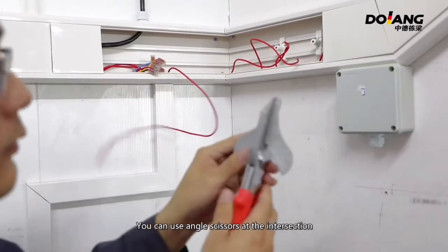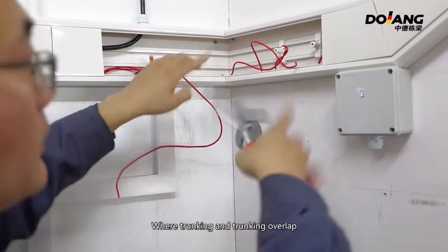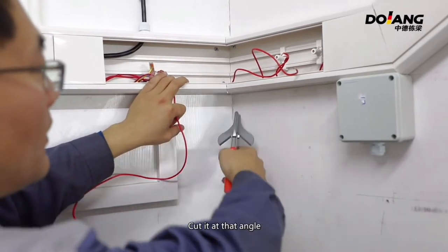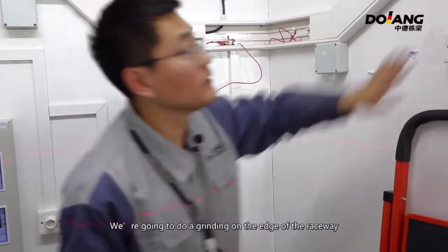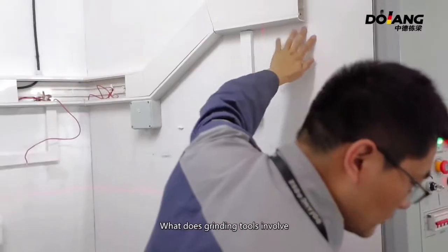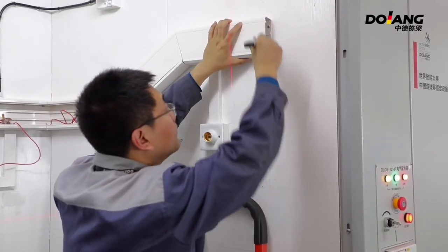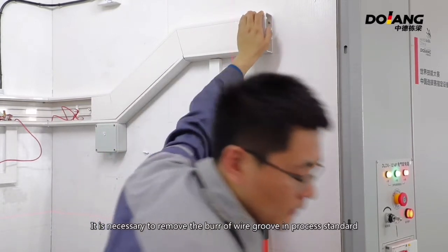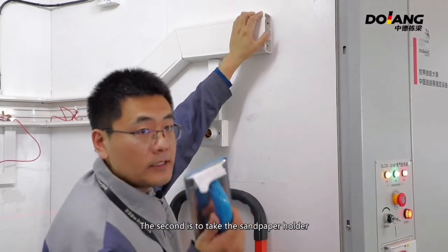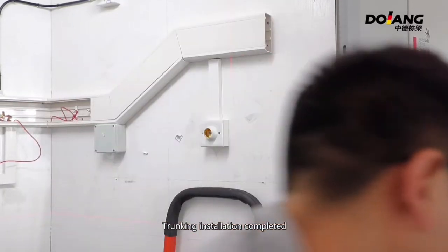You can use angle scissors at the intersections. When trunking sections overlap, cut at the angle. After cutting, install the trunking on the wall. This is an angle scissor tool. Whenever the side raceway is installed, we do grinding on the edge of the raceway. Grinding involves using a ceramic scraper to remove burrs from the wire groove as per process standards. The second step is to take the sandpaper holder and sand the side of the raceway. After polishing, trunking installation is completed.